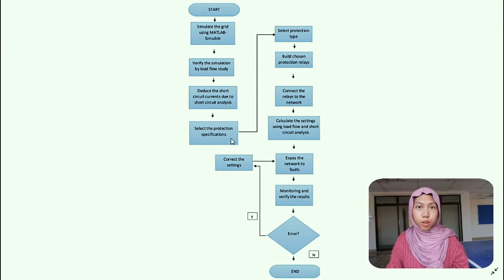After that, we proceed to select the protection system or type that are going to be used in the system, such as relay. After the relay has been chosen, we apply the relay to the entire system and we verify the calculation using both load flow and short circuit analysis.